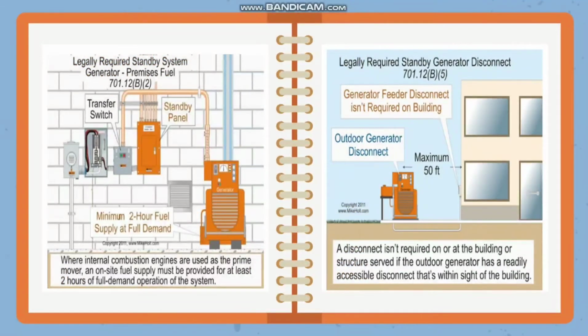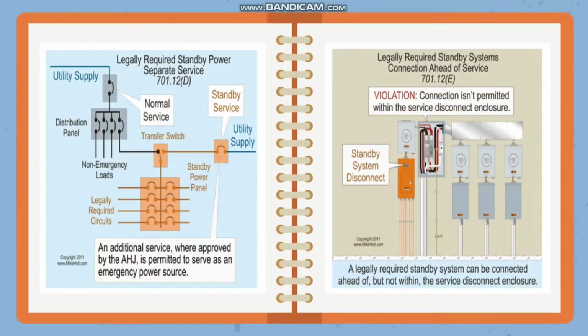Legally required standby system generator, premises fuel, where internal combustion engines are used as the prime mover, and on-site fuel supply must be provided for at least 2 hours of full demand operation of the system. Next, legally required standby generator disconnect. A disconnect isn't required on or at the building or structure served if the outdoor generator has a readily accessible disconnect that's within sight of the building. So next, legally required standby power separate service. An additional service where approved by the authorities having jurisdiction is permitted to serve as an emergency power source. Legally required standby systems connection ahead of service. A legally required standby system can be connected ahead of but not within the service disconnect enclosure.